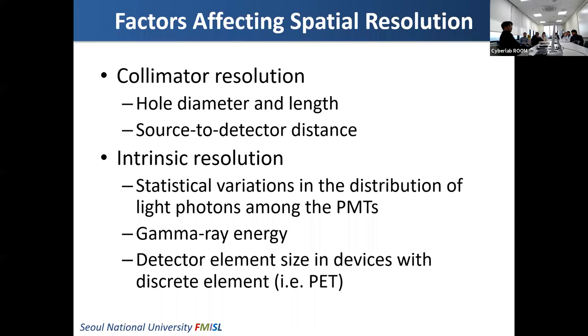Some geometric factors are also important. The photomultiplier tube has its best gain at the center, but between the photomultiplier tubes we lose a lot of light. That also causes some variation in light collection. Another factor is the gamma ray energy.